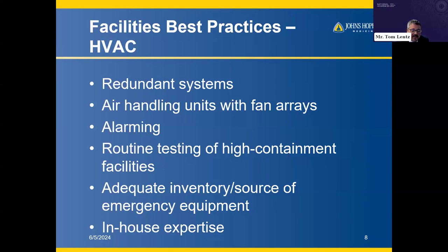Got a little ahead of myself, but we do full testing of our high containment facilities—a full shutdown scenario to make sure all systems respond the way they should. There are always full exhaust redundancies in high containment areas; one protects the other, but if both go down, it also slams the supply shut to create, at worst, a neutral environment, which is again protective for everyone.